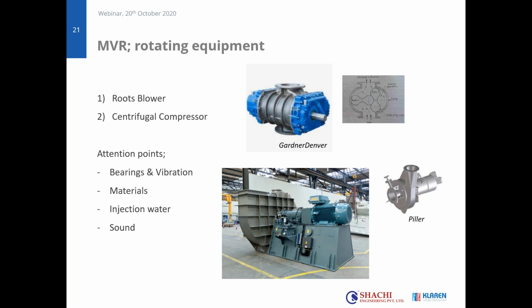This roots blower is able to handle a wider range of compressor ratios, because the compressor ratio comes more from the systems before and behind than from the compressor itself. Based on tight clearances, there's less leak flow, so it can handle higher compressor ratios compared to the centrifugal one. A roots blower just has normal roller bearings, so in that sense it is also a bit easier.